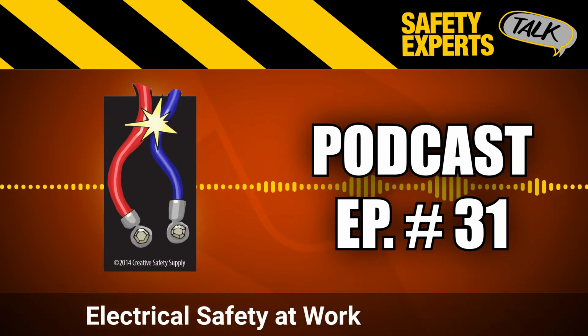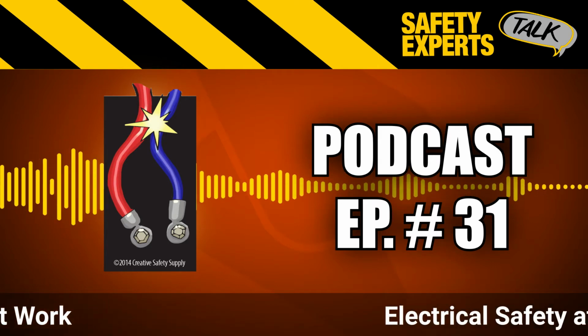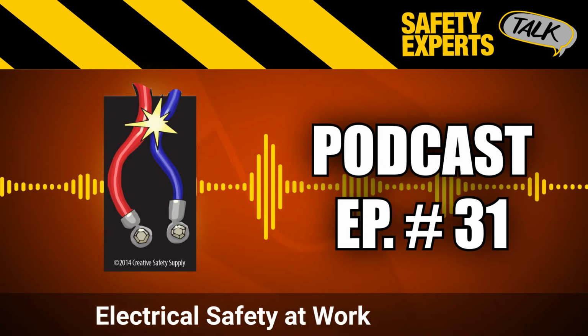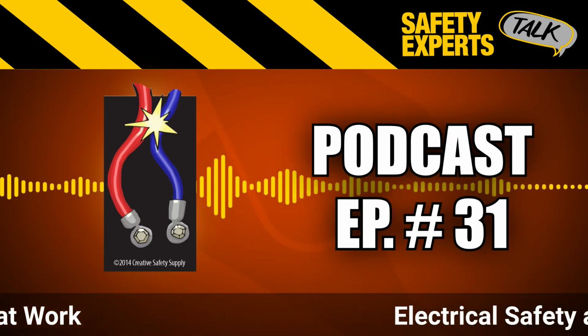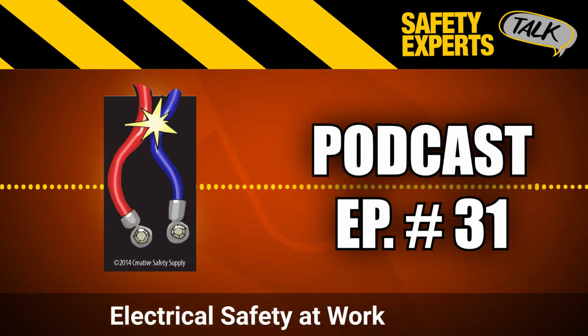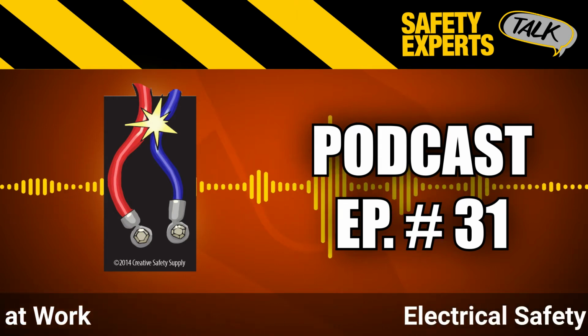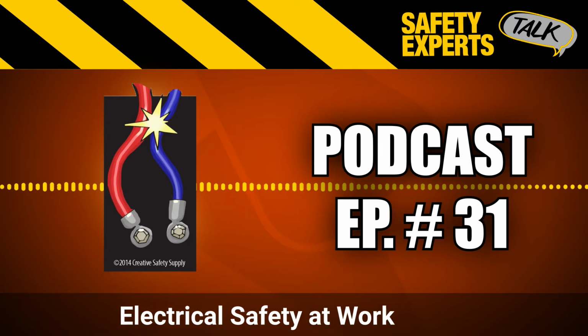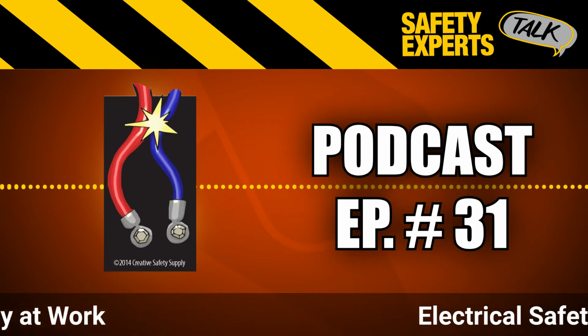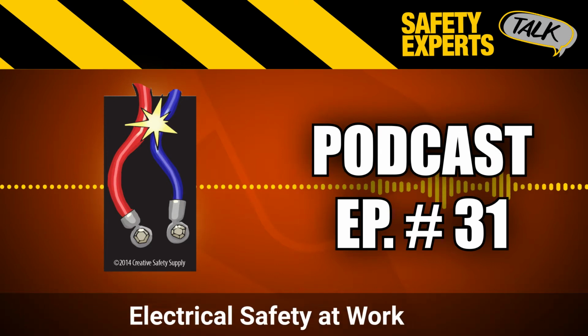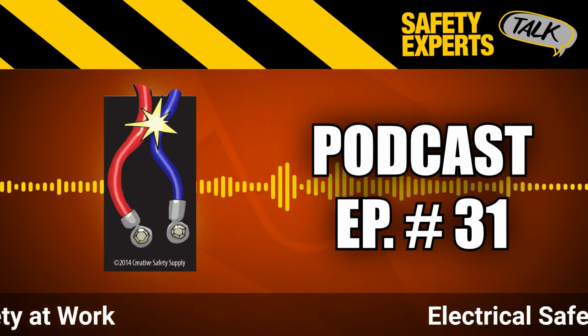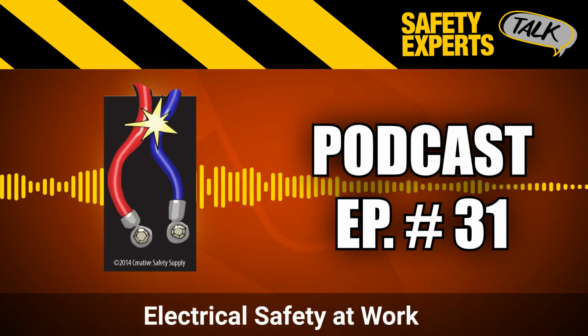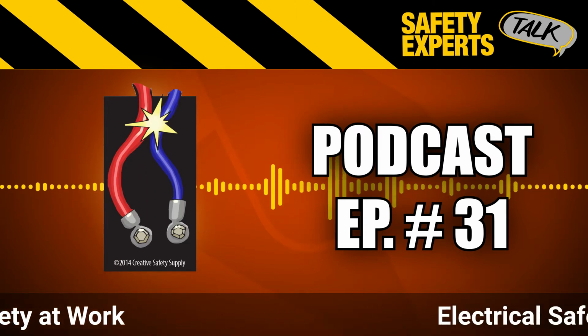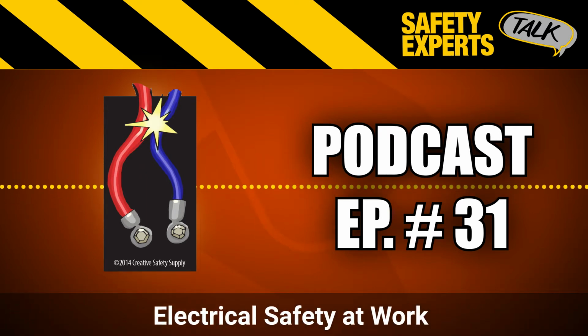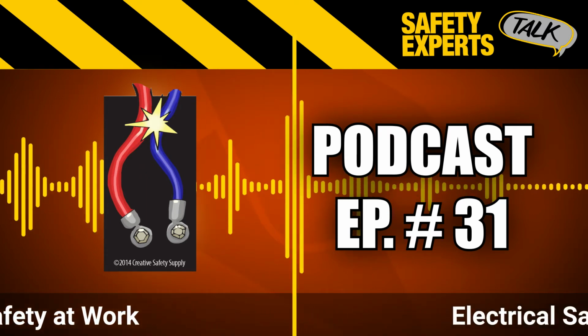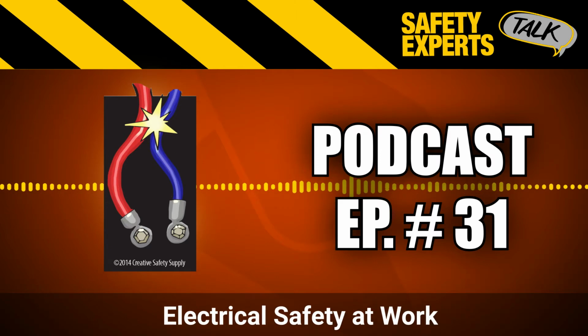Yes, I guess some of the issues I've probably seen is more the verification stage of electrical lockout tagout, which includes that a worker verify that the equipment is properly de-energized. Sometimes the equipment will just be de-energized and then they'll think to go to work instead of having a qualified electrician verify with a multimeter to check that panel board is actually de-energized so that the worker can safely work on that equipment.